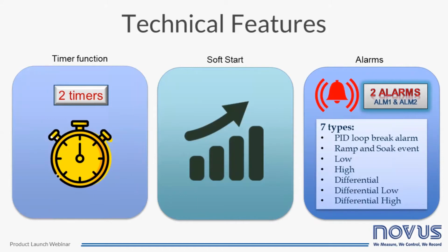The controller has 2 timers, timer 1 and timer 2, which operate independently of temperature control actuation. The time count always starts with timer 1, and at the end of it timer 2 starts counting. The time base can be set as minutes or seconds. Any of the controller outputs can be linked to the timers. There are 3 trigger options for timer 1: by temperature reaching set points, by pressing the F key, the function key, or by starting the run control. Timer 2 is a secondary timer, which always starts its counting at the end of timer 1. For both timers, time counting can be set in ascending or descending mode, and this will be shown in the display.